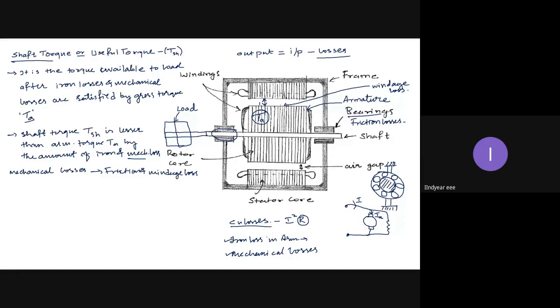windings start conducting the current, copper losses will occur, iron losses will occur. These losses will heat the iron structures and winding structures, and that heat starts getting dissipated to the outer atmosphere. Now, whatever heat is produced on the outer surface of the armature and the inner surface of the field will try to dissipate in the air gap, because of which the air starts getting heated up.